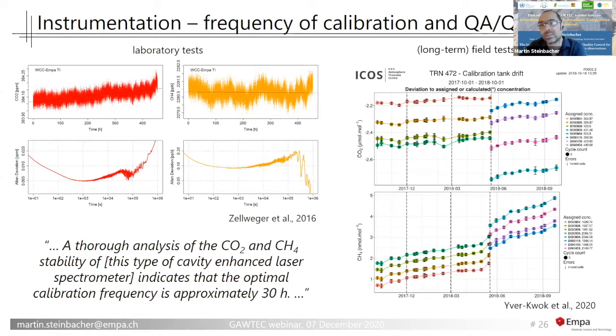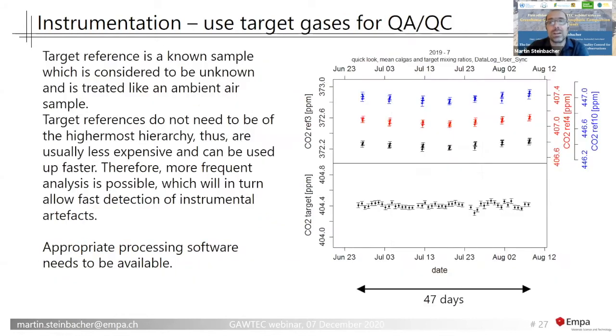But in addition, there are some target measurements done. A target gas we see here in the lower panel. In the upper panel, we see again 3 calibration gases measured every 5th day. And in addition to that, we have a target tank that is measured at least once a day for rapid detection of some instrumental artifacts. Because if you calibrate every 5th day, or in the ICOS example only every 2nd week, you will only realize after 10 days or 2-3 weeks that there was something going wrong.